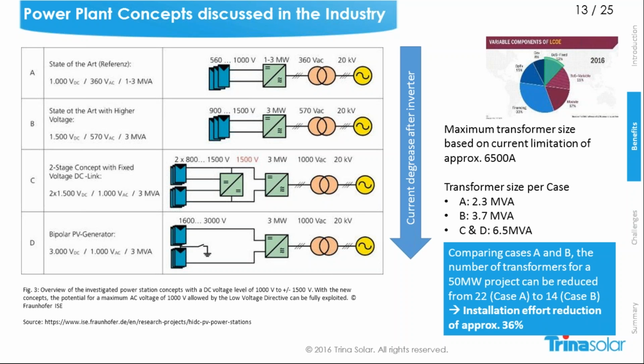If you now only look at cases A and B and compare them, assuming we have a 50 megawatt project, in case A we will need 22 transformers. In case B with the 1500 volt system, only 14. That means the installation effort for the transformer, which is approximately the same per piece, even if they have a different capacity, can be reduced by up to 36% based on these numbers, which means your fixed BOS, your capex, will be reduced. That shows that the 1500 volt system also enables new power plant concepts, which leads to further cost reductions.